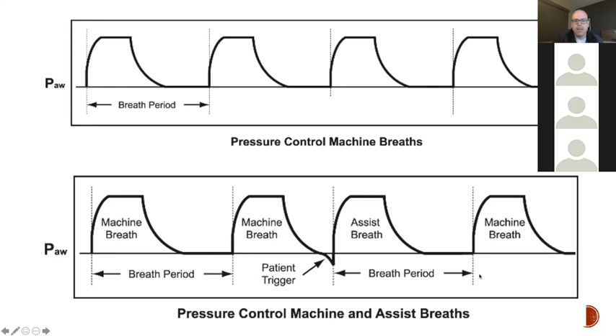So this is what SIMV would look like. The machine gives them a breath, then it went along, it was time for another one, so the machine gave them a breath, then they tried to take a breath. When they tried to take a breath, the machine kicked in and gave them that fully assisted breath. But then they said they wanted another one. Well, it's not time yet for another one. So the machine just gave them, you'll see it here, a little bit of pressure support. And that pressure support allowed them to not feel like they were suffocating. But you can see they didn't take a full breath here. They just took a little supported breath.